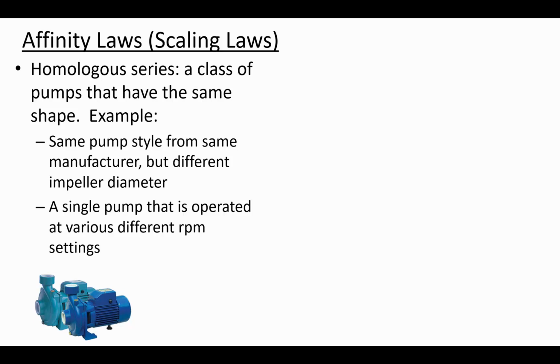Another common illustration is that most pumps are originally designed to operate at a certain RPM, but you can add a variable frequency drive, and with that you're essentially changing the frequency that the electricity is going into the motor. Rather than being 60 hertz, if you give the electricity at 50 hertz, it's going to slow down the motor, and therefore reduce the rotational rate of the pump. Either one of those things is going to change the original performance that you had.